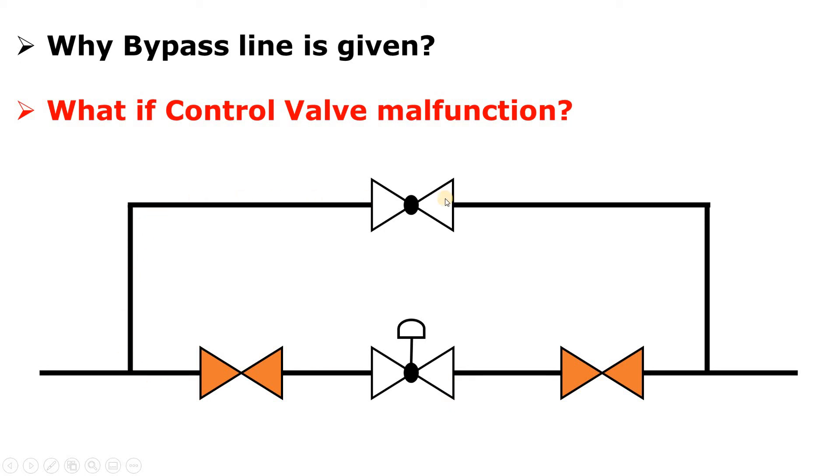That time also, isolate this control valve and open this bypass valve. Many times I have seen that we do not know about it. That is very, very important: why the bypass line is given.